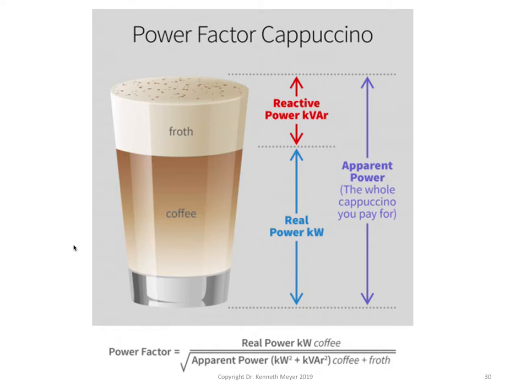Now, the supply authorities, as I mentioned, like you to keep your power factor at about 0.9 or 0.95, and if you don't, they have two charges that they use. They have the kilowatt charge, which is the real power, and they have a kVAR charge. So the more kVAR you have, they charge you a lot of money.